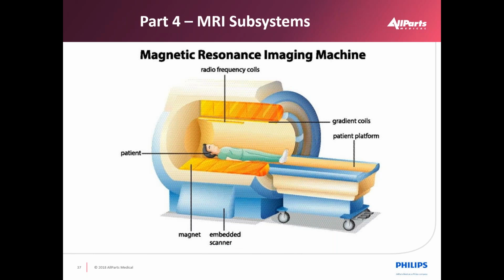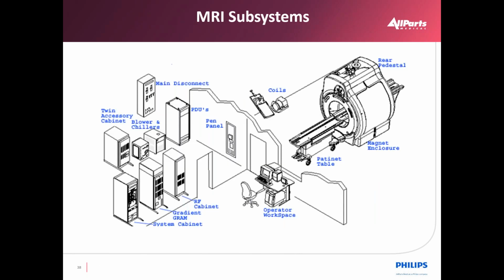Part 4, MRI subsystems. This is a generic breakdown of the 3 areas used for the MRI equipment. The first is the system operator area, which has the MRI host computer and viewing station. The second is the equipment room with the required system components. The third is the MR magnet, which is an RF shielded room to prevent external RF noise and also prevent artifacts from showing up in the image.